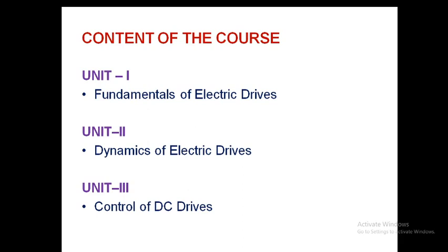When both torque and speed are in reverse, then it will enter into the third quadrant. That is the reverse motoring mode. Now from reverse motoring mode, again, if you reverse the speed, now the speed is in the negative direction. If you bring that speed into the positive direction, that is a reversal of speed, right? It will go to the fourth quadrant. That becomes the reverse braking. So these things we'll see by drawing the characteristics also. If you understand that fundamental torque equation, from there only we will draw the characteristics.